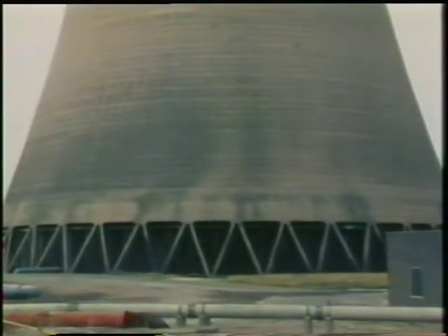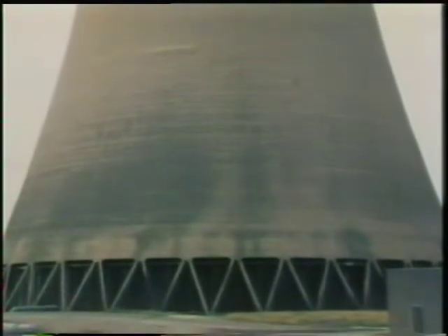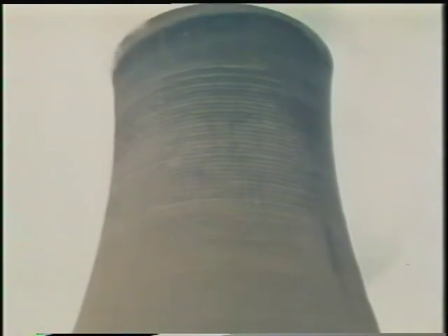Inside the towers, the condenser circulating water falls like rain, and it's cooled by a current of cold air passing up the tower. The water came out from the condenser at about 30 degrees C, and this cools it to about 20 degrees C, ready to go back again. The water is sprinkled down from about a third of the way up the tower. Above this, there's just a great hollow space. The sides are curved inwards near the top, and it's this particular shape which produces a constant flow of air drawn in at the bottom and out at the top.